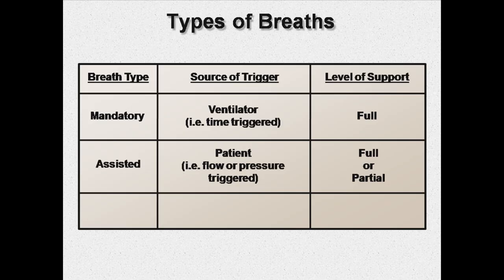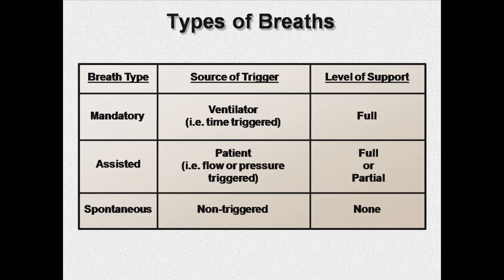Ventilator modes also distinguish between three different types of breaths. Mandatory breaths are triggered by the ventilator and receive a full level of support — the number of mandatory breaths per minute is dictated by the respiratory rate set by the clinician. Assisted breaths are triggered by the patient and may receive either full support or only partial support. Finally, spontaneous breaths are those which the patient takes which do not trigger any response from the ventilator and therefore receive no support. Most modes allow fully supported assisted breaths to count as mandatory breaths in order to improve patient comfort, prevent patient-ventilator desynchrony, and prevent hyperventilation.